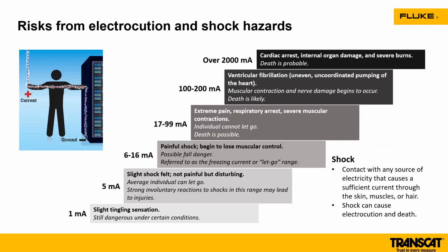If you look at electrocution and shock hazards, this is a great slide that I like to show. There was a study done many years ago, and basically they studied what the feeling was when they gave a certain amount of current through the body. As you can see, at 1 milliamp, there was a slight tingling sensation. Where we get into that 5 milliamp range, a shock was felt, but it wasn't painful. And it's ironic that typically our GFCIs in our bathrooms and in our kitchens are rated at that 5 to 6 milliamp mark. But as we jump up that scale, you can see that the shock becomes more painful.